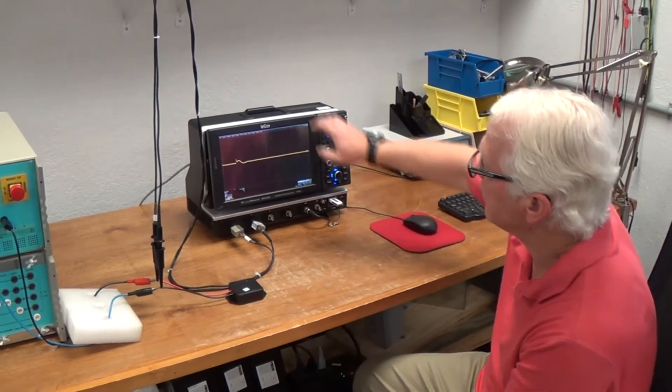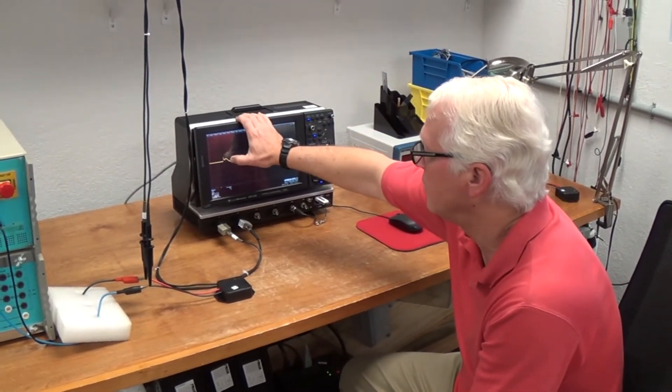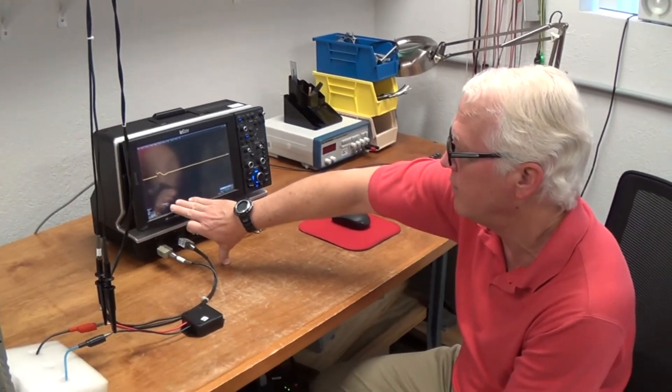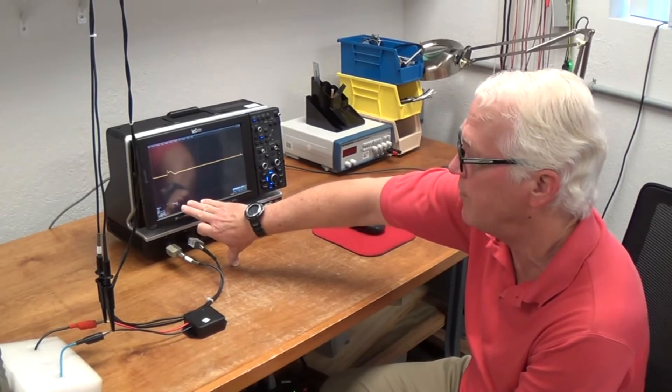Okay, there you go. So this surge would have gone to 2,000 volts. After it goes through our filtering circuitry, the let-through voltage will be only 32 volts.